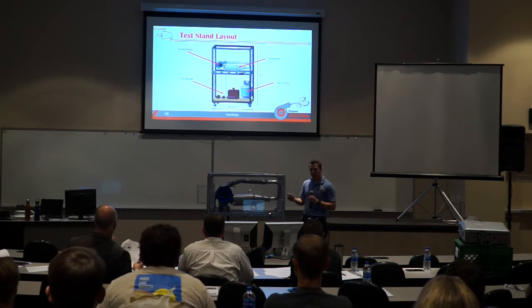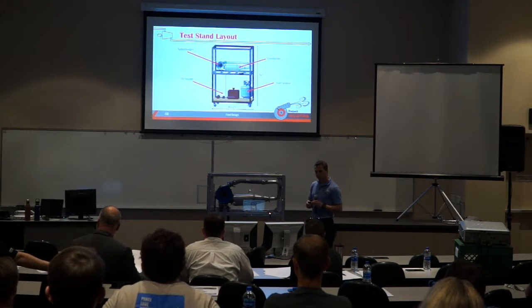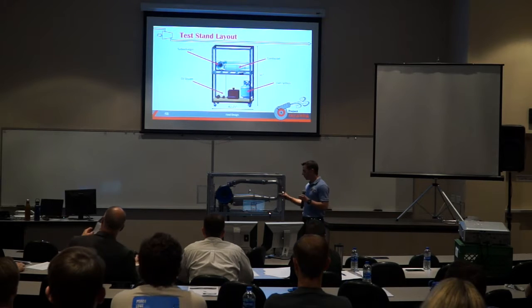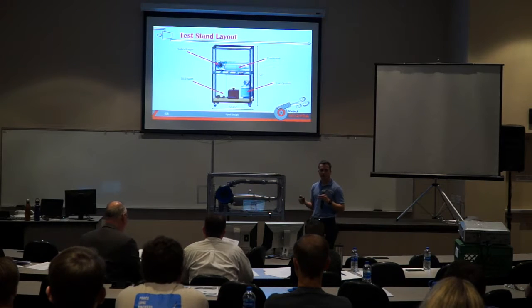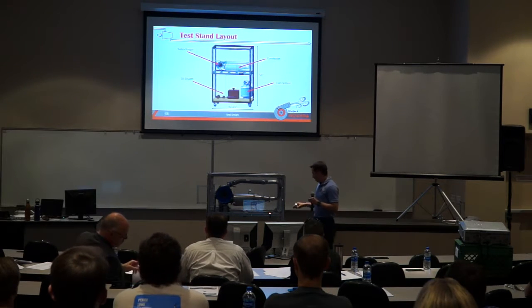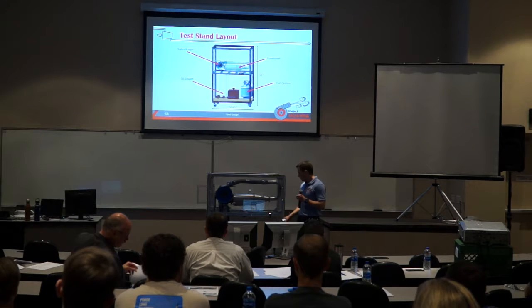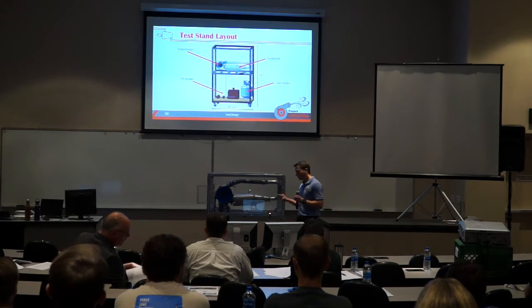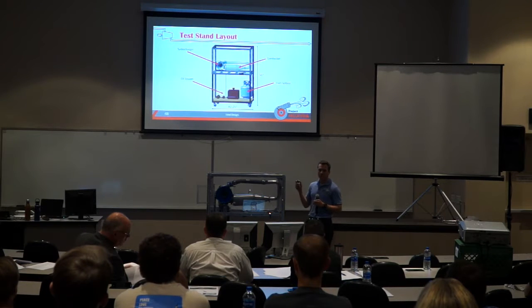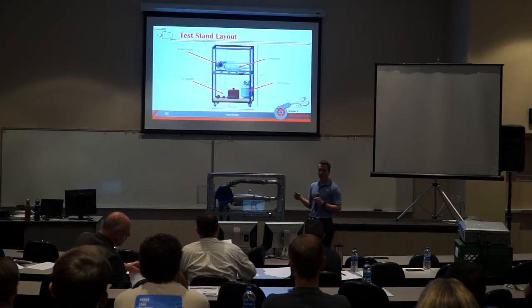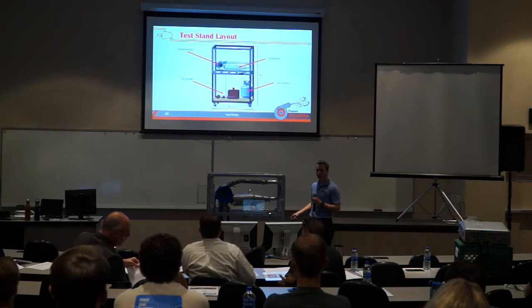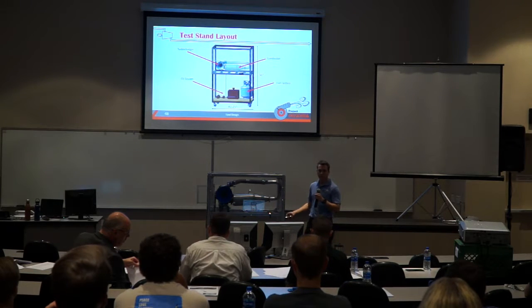As I said earlier, we had two degrees of separation between our fuel source and the combustor, which is mandated by OSHA and ASME standards. Our fuel source was on the bottom, and the two degrees of separation were through our fuel regulation valves and the vertical distance. The vertical distance helps prevent reverse flow, also guaranteed by the pressure regulator on top of the fuel source.